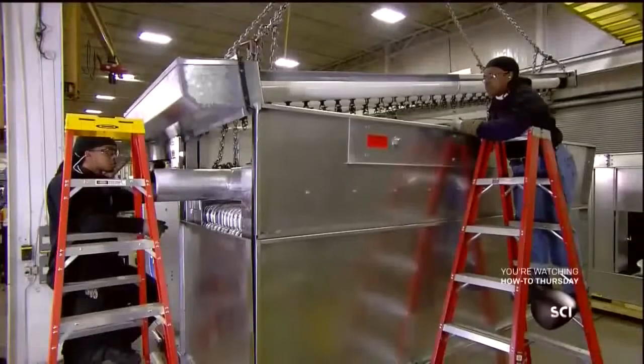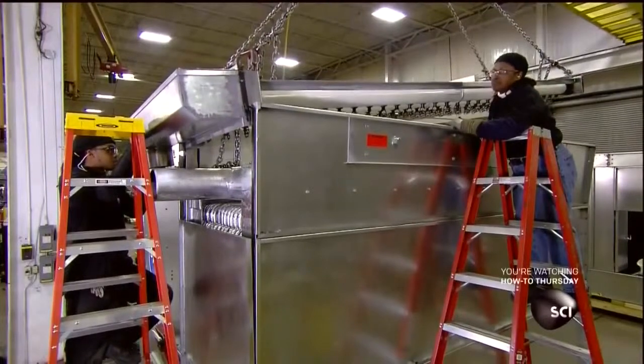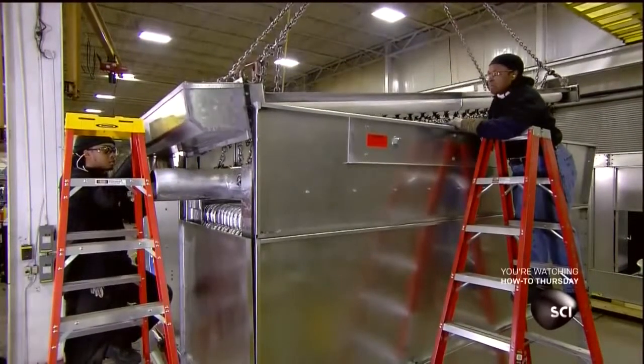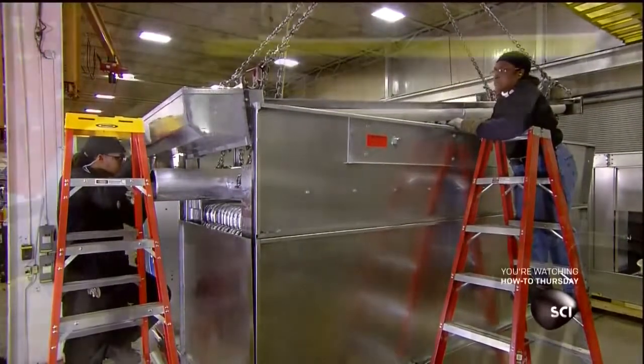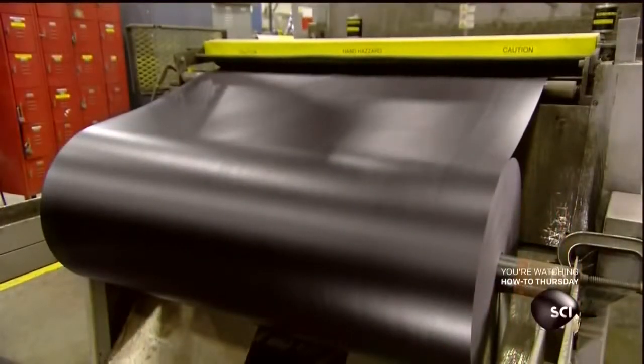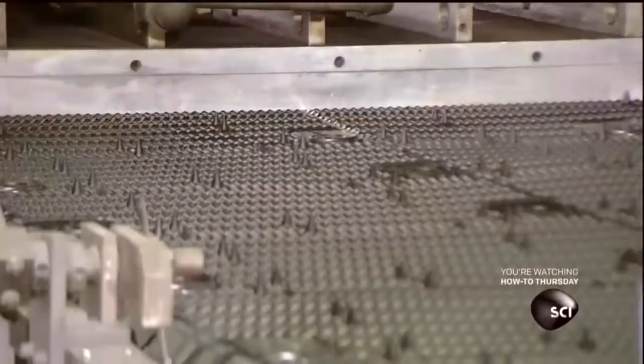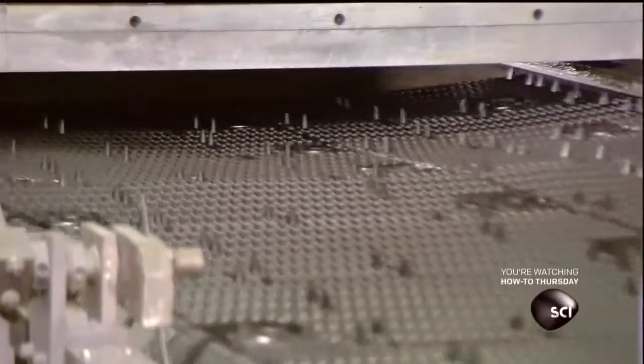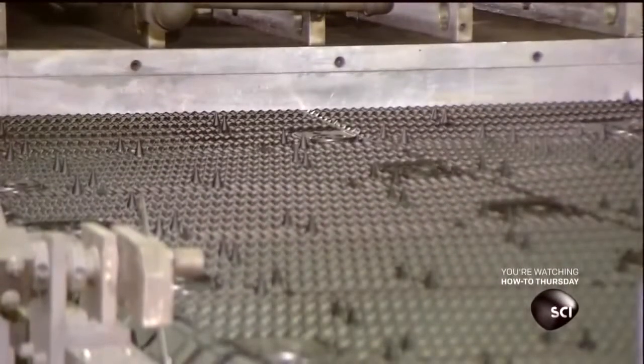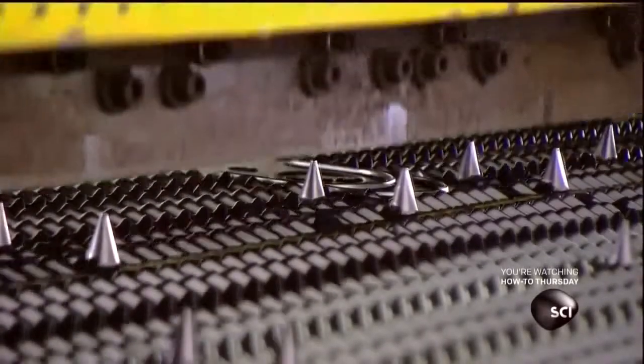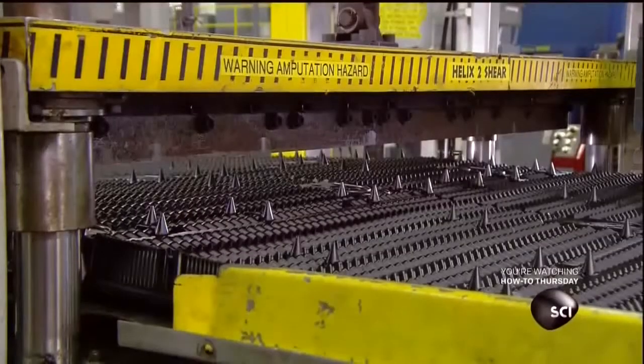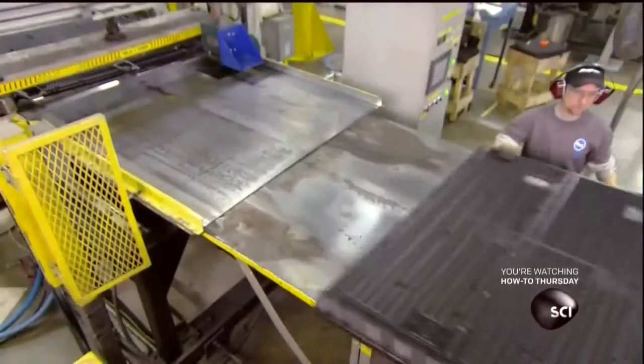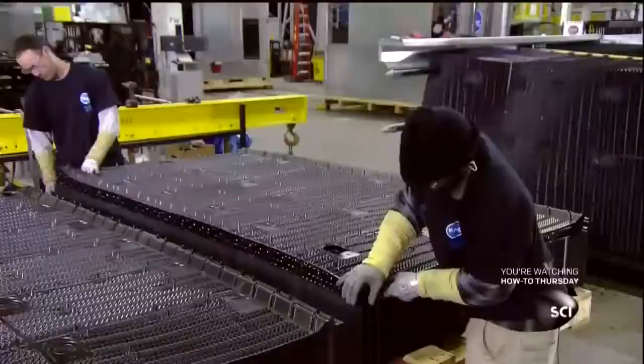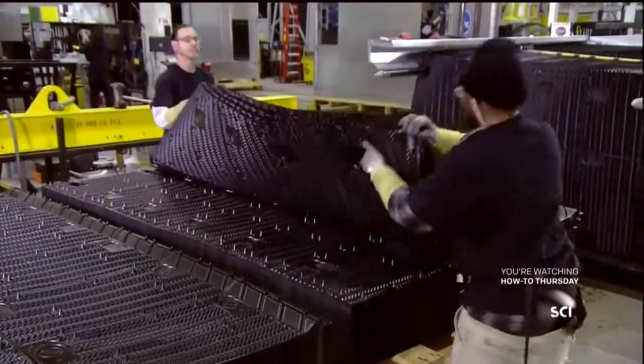The sprayed cold water absorbs the heat from the fluid circulating through the coil. The fans then cool the water by evaporation as it flows downward through a bundle of PVC sheets. The machine first heats the PVC to soften it, then stamps it with a mold plate. This imprints a proprietary pattern of peaks and valleys. This pattern is the secret to the evaporative cooling process because it moves the air and spreads the water in a way that maximizes efficiency.